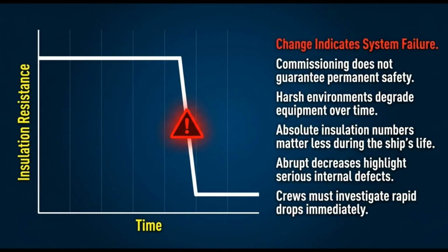Monitoring is continuous. Since equipment degrades over time, crews must investigate any abrupt drops in insulation resistance immediately to identify internal defects before failure occurs.